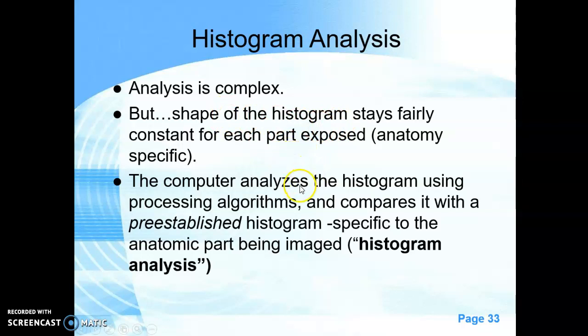So the computer analyzes the histogram using processing algorithms, compares it with a pre-established histogram, which is comparable to a part that you're imaging. This is called histogram analysis. So you're going to pick the exam and the projection or part or view that you're performing.